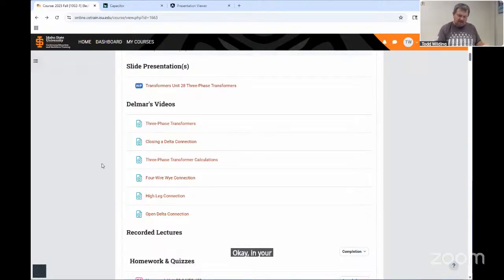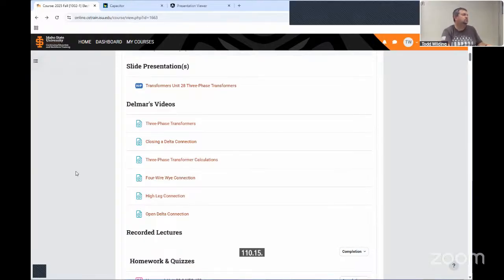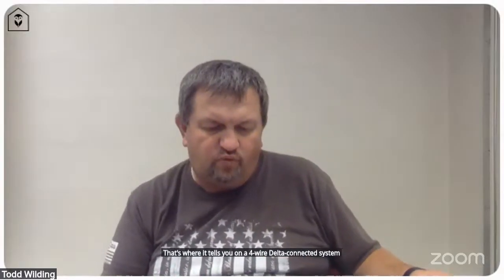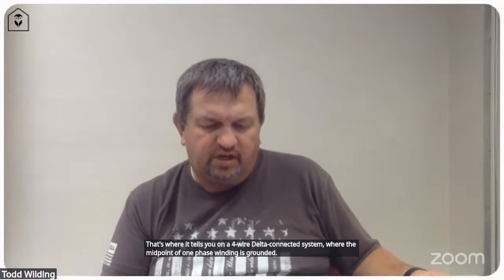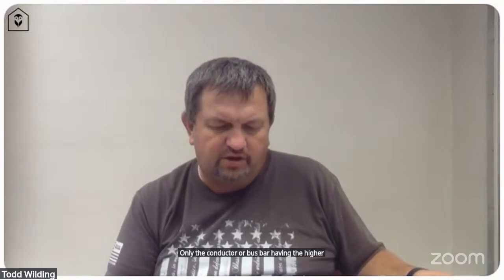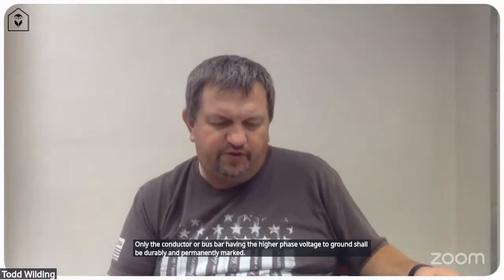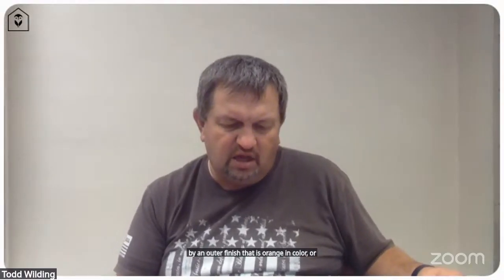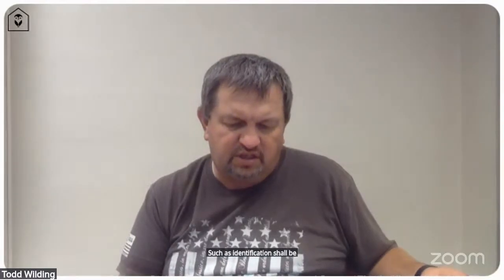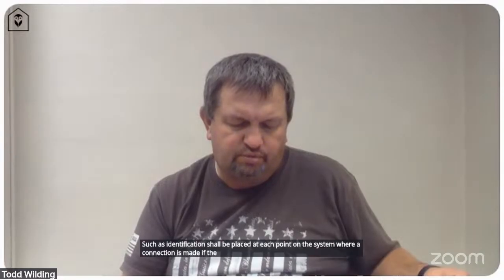Okay, in your code book, 110.15. That's where it tells you on a 4-wire delta connected system where the midpoint of one phase winding is grounded, only the conductor or bus bar having the higher phase voltage to ground shall be durably and permanently marked by an outer finish that is orange in color or by other effective means. Such identification shall be placed at each point on the system where a connection is made if the grounded conductor is also present.